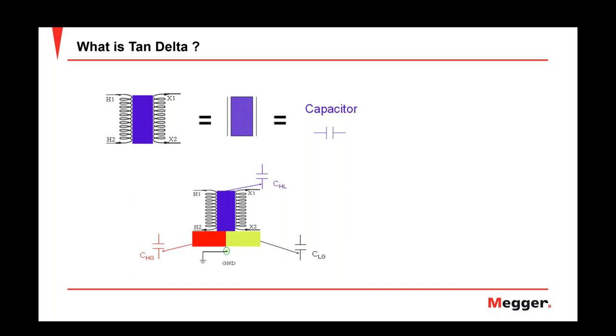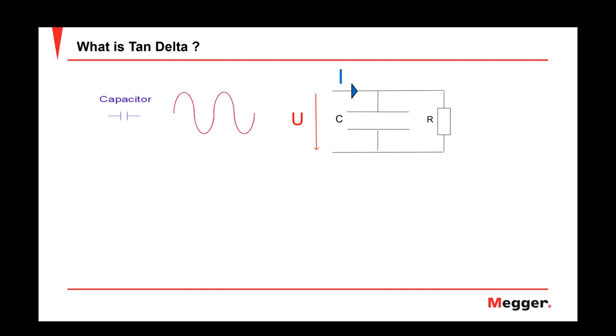This capacitor is not only located between the high voltage winding and low voltage winding — we also have two more: between high to ground, and low to ground. So we have several insulation points, which could be paper, oil, spacers, barriers, whatever. When we apply AC voltage to this insulation modeled as a capacitor, we drive current through both the resistance and capacitance. The angle between the total current and voltage gives us a very small angle, typically 0.4–0.5 degrees, called delta.